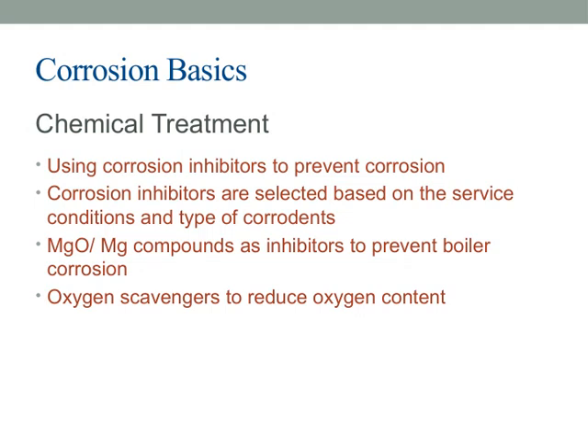Let's talk about chemical treatment as a key strategy in corrosion prevention. One of the main approaches is using corrosion inhibitors, carefully selected based on the specific service conditions and the type of corrodents involved. For example, magnesium oxide and magnesium compounds are often used as inhibitors to prevent corrosion in boilers, helping by forming protective films that reduce the metal's exposure to corrosive agents. Another important chemical treatment involves oxygen scavengers, which work to lower the oxygen content in the system. Since oxygen is a major driver of corrosion, especially in water systems, removing it significantly slows down the corrosion process. Overall, chemical treatment is a vital part of corrosion management strategy, tailored to the particular environment to effectively minimize damage and extend equipment life.